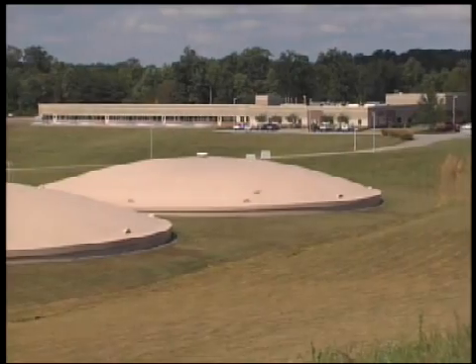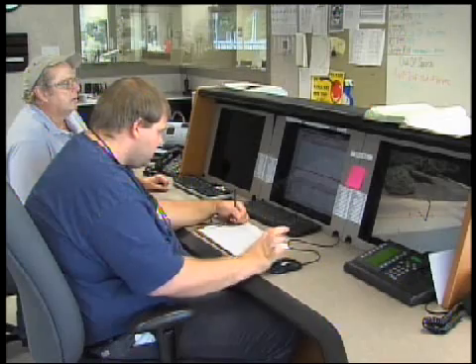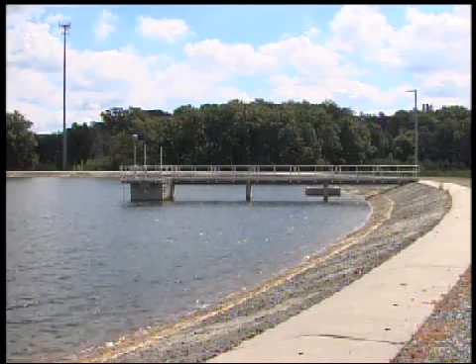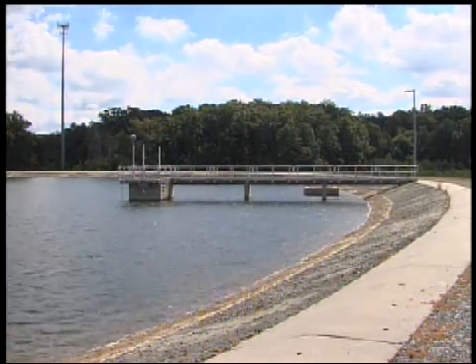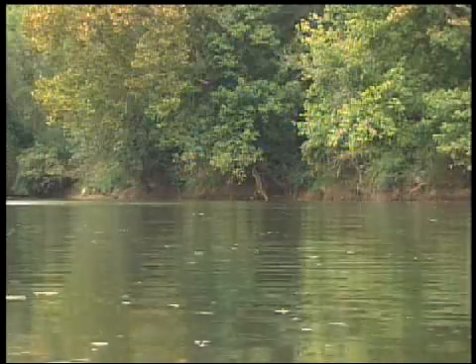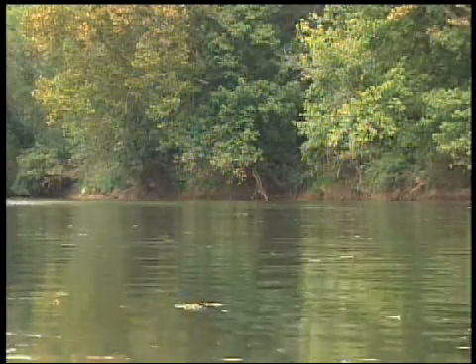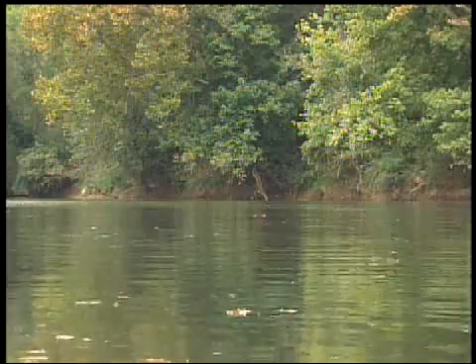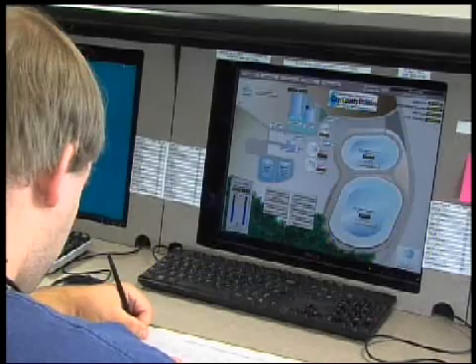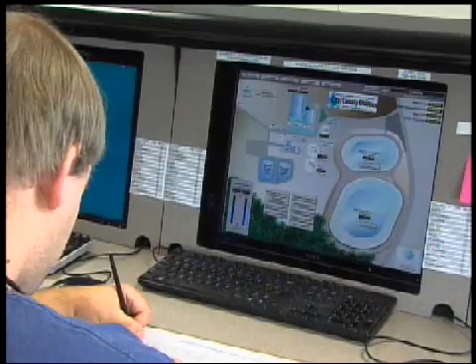Operators can intervene at any point if they have to. Operators can also control when the intake pumps pull water out of the river. That six-day supply in the raw water reservoirs gives operators flexibility in deciding when to pump water out of the river. If the river is especially muddy from runoff after a storm, operators can wait a couple of days for the river to clear. More importantly, it allows the plant to keep operating if the river is contaminated upstream.